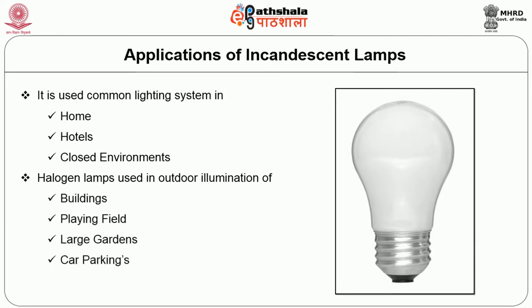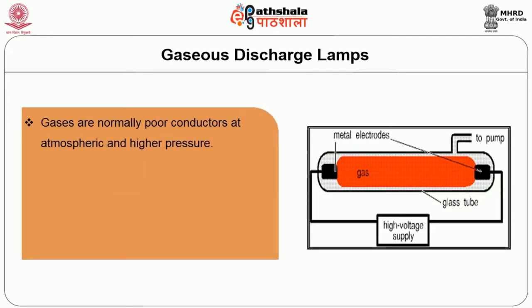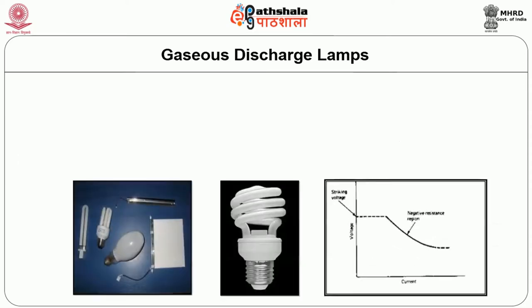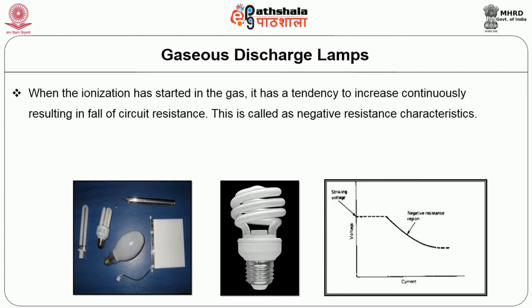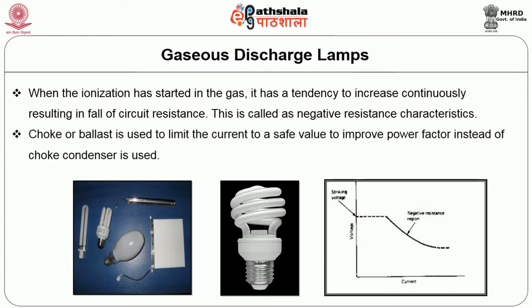Gaseous discharge lamps: gases are normally poor conductors at atmospheric and higher pressure. With the application of a suitable voltage called ignition voltage across two electrodes, there will be a discharge through the gas accompanied by electromagnetic radiation. The wavelength of this radiation depends on the gas, its pressure, and the metal vapor in the lamp. Argon gas, sodium, and mercury vapor gas are commonly used. When ionization has started in the gas, it tends to increase continuously, resulting in a fall of circuit resistance — this is called the negative resistance characteristic. A choke or ballast is used to limit the current to a safe value. To improve power factor, a condenser is used instead of a choke.